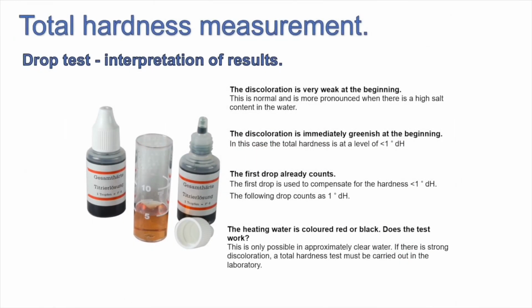Interpretation of the results. This discoloration is very weak at the beginning. This is normal and is more pronounced when there is a high salt content in the water. If the discoloration is immediately green at the beginning, in this case the total hardness is at a level of less than 1 German degree. The first drop already counts. The first drop is used to compensate for the hardness of less than 1 German degree. The following drops count as 1 German degree.